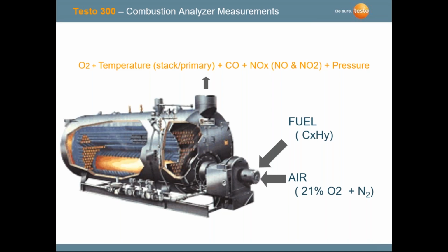You see that NOx, and then you see in parentheses NO and NO2. NO is nitric oxide. NO2 is nitrogen dioxide. The combination of both NO and NO2 equals the NOx. That's where you get the NO, and then you get the subscript X. Primarily on boilers and furnaces, 95% of the total NOx is coming from what we call the NO sensor. The other balance, which would be 5% or less, is coming from NO2.